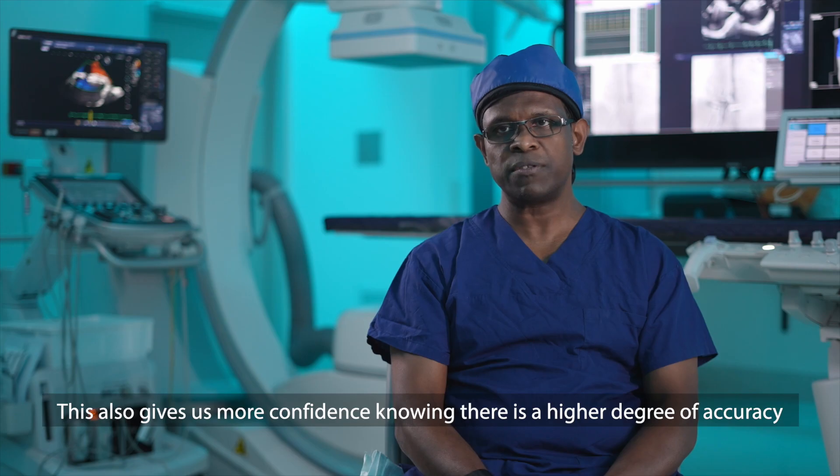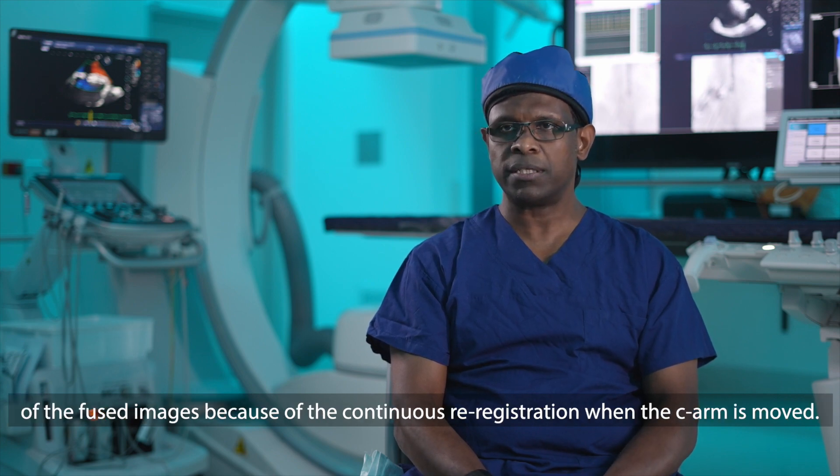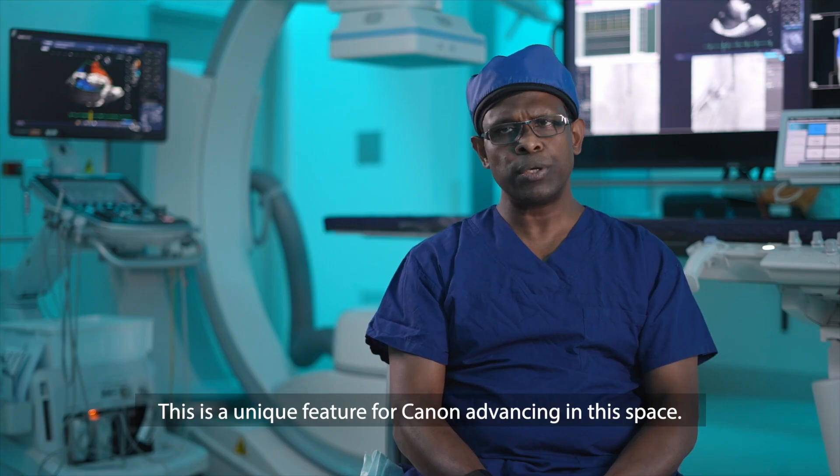This also gives us more confidence knowing there is a higher degree of accuracy of fused images because of the continuous re-registration when the C-arm is moved. This is a unique feature for Canon advancing in this space.